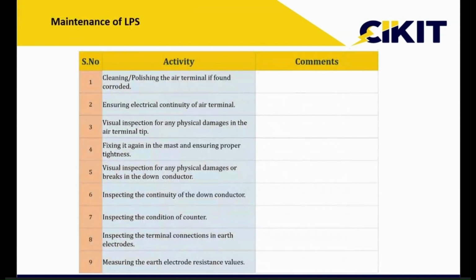Right. So if we take this lightning protection system, we are doing nothing other than providing a dedicated path for this lightning impulse current to discharge. So the continuity plays an important role. We need to ensure that from the tip of the air terminal to the earth electrode, all the connections are proper. There are no loose connections in between. So continuity is the most important parameter when it comes to the air termination system and down conductor system. If the continuity is proper, then the system will definitely work fine. So we need to ensure all the connections are proper, and all the clamps are in good condition.